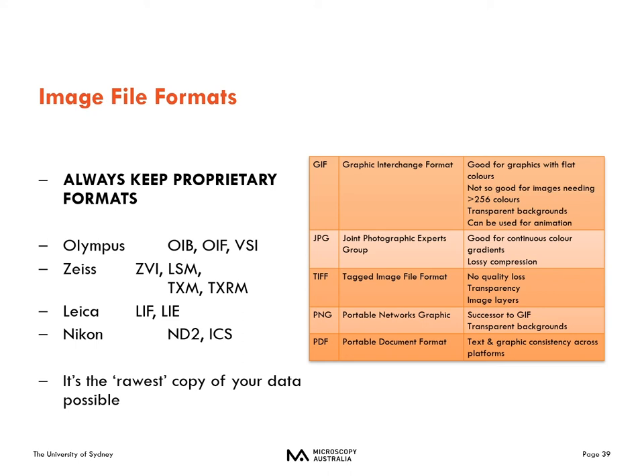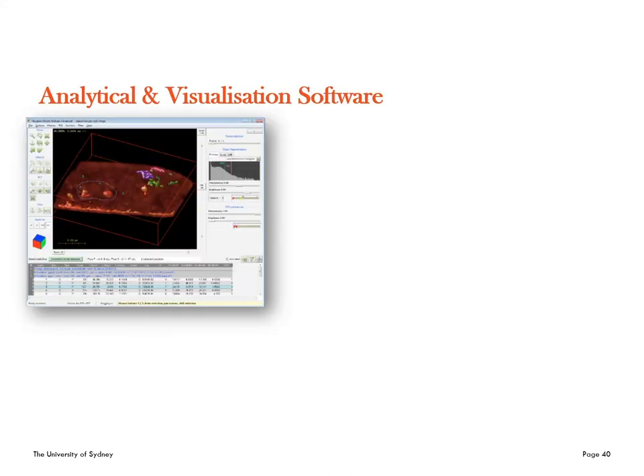Now this could be real — it has happened before — but it's also strange. So I looked at the image metadata and there wasn't any. It was a simple 1024 by 1024 image with no data embedded. It was also pure black — it looked as if someone had opened up a paint program, made a 1024 by 1024 image with a black background, and used this as a background control image. I'm not saying this to scare anyone, but always save the data in the proprietary format and you won't have any issues like this.